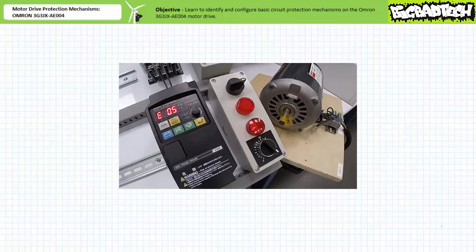About a minute or so into the experiment, the drive powers off the output and faults out. The data display says E05, corresponding to an overload trip as anticipated. Note the alarm LED on the drive is illuminated. Rather than switching a pilot light using the constant speed arrival function, the multifunction electromechanical relay output could be put to better use switching a brake solenoid using the alarm output function to lock the de-energized motor in place for emergency purposes if the application warranted this level of protection.